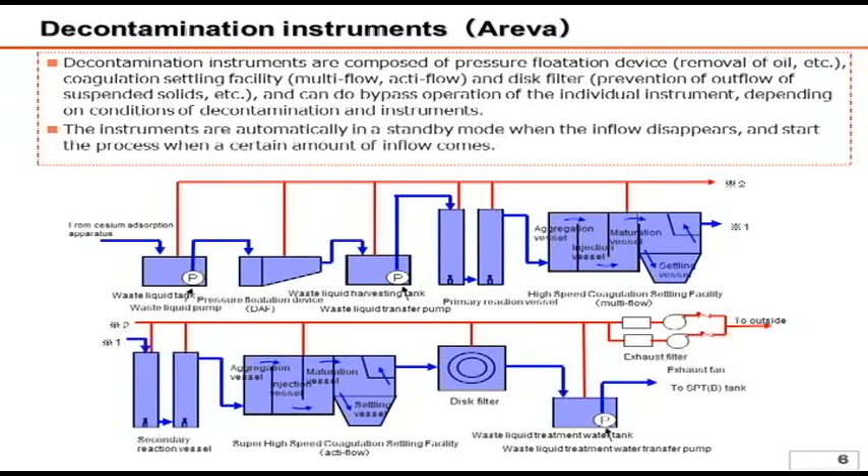The resulting product is stored in the settling vessel. The chemicals are added again to the clear supernatant water for further coagulation. After those treatments, the treated water is transferred to the SPT(D) tank. The red line indicates the exhaust system using a fan in order to prevent a high concentration of hydrogen and oxygen inside the tanks, which may be produced due to radiation decomposition in the liquid treatment.